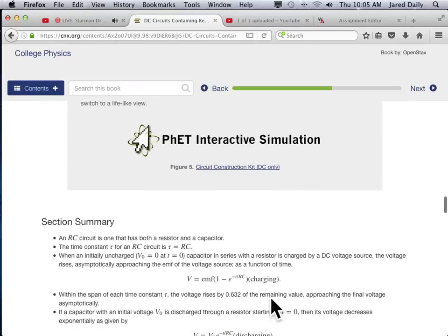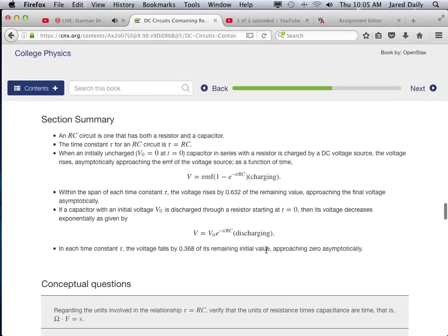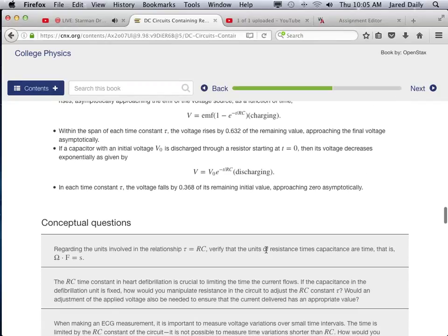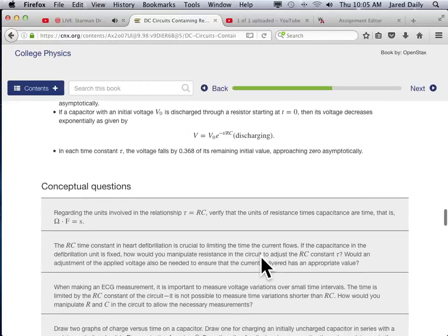And you want that big voltage drop in that short time for a defibrillator so that you get a very quick energy jolt to the heart. You don't want it to be too long, because if you have a long energy jolt, then you have a long time that current's going through, and it'll cook your heart. But if it's a very short time with the right voltage and the right current, it doesn't have time to cook anything, it just gets things started again.